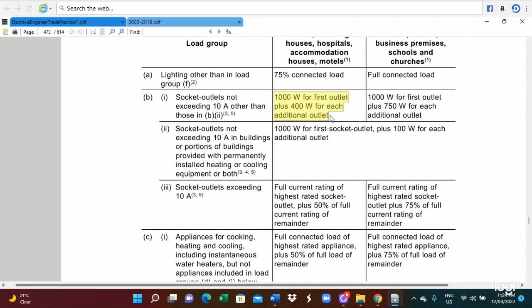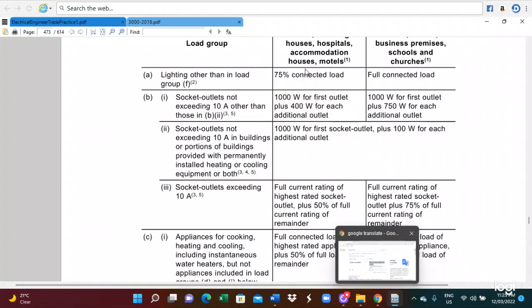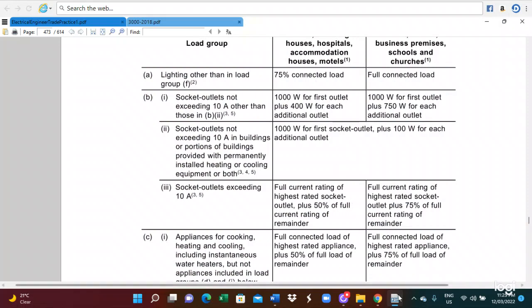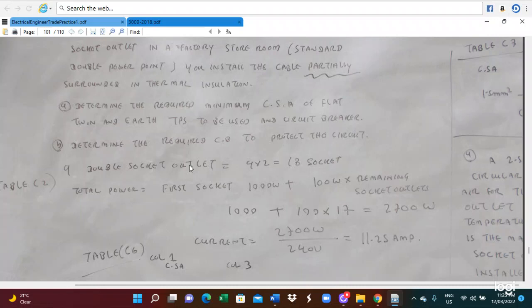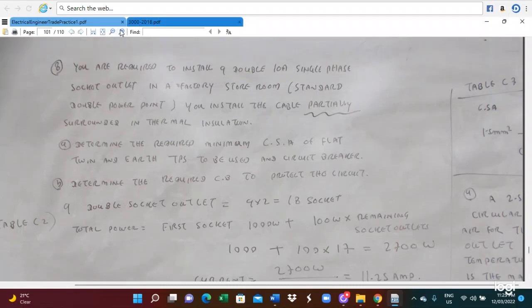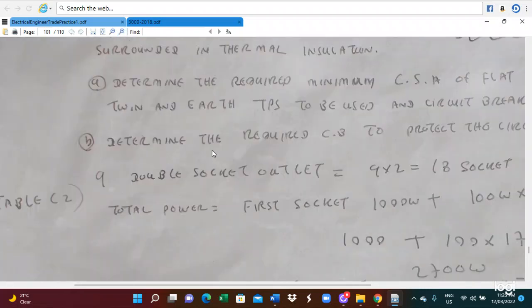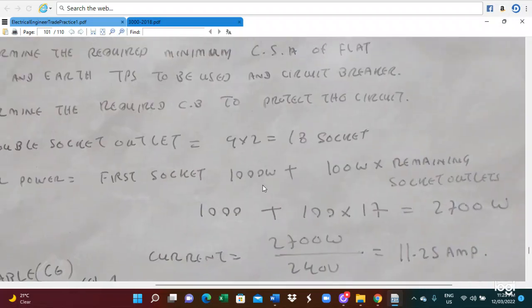So for the first socket outlet we take 1000 watts, and add 400 watts for each additional socket outlet. This is the rule given, using the factory law from table C2. So table C2 gives the first socket outlet value, and then we multiply 100 watts by the remaining socket outlets.